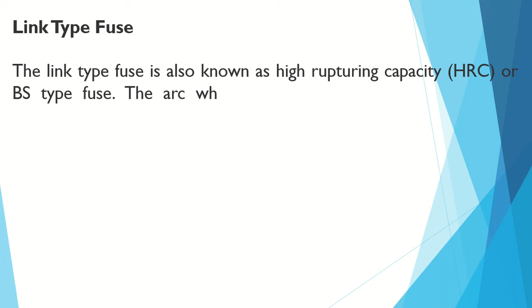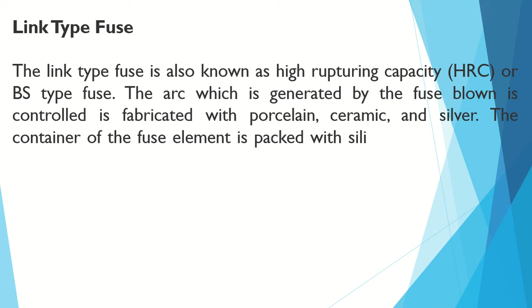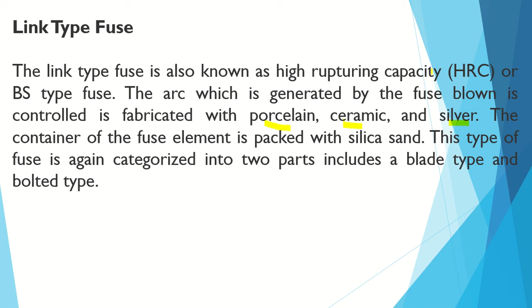Link type fuse. The link type fuse is also known as high rupturing capacity HRC or BS type fuse. The arc which is generated by the fuse blown is controlled. It is fabricated with porcelain, ceramic and silver. The container of the fuse element is packed with silica sand. This type of fuse is again categorized into two parts such as blade type and bolted type. It's also known as high rupturing capacity fuse or HRC fuse or BS type fuse. Okay. And what is blade type and bolted type fuse, right?